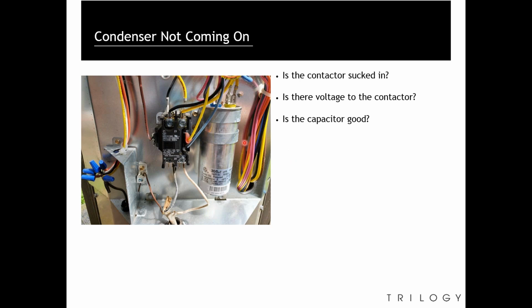Is the capacitor, is it good? If the compressor is working and the fan is not, or vice versa, chances are it's the capacitor. Now, does your system have a pressure sensor? If so, we want to make sure there's pressure in the system. If there's no system pressure, it won't kick on because of that sensor. So you always want to double check on that.